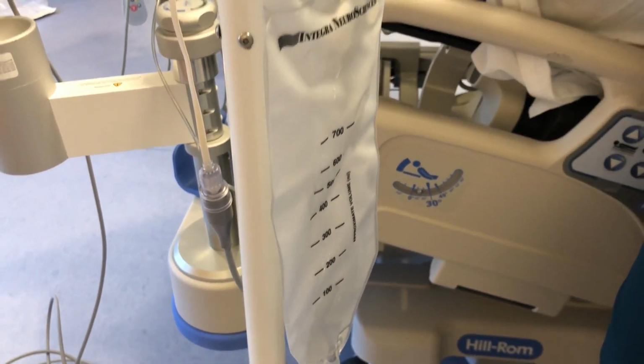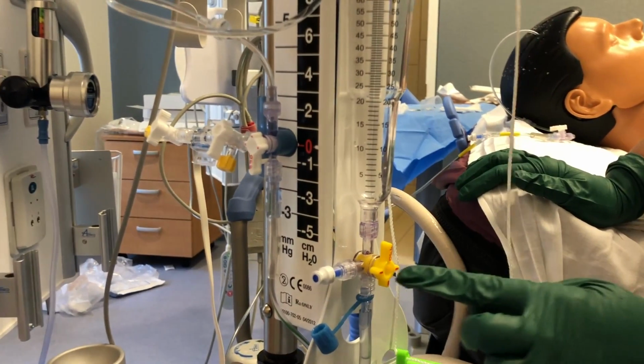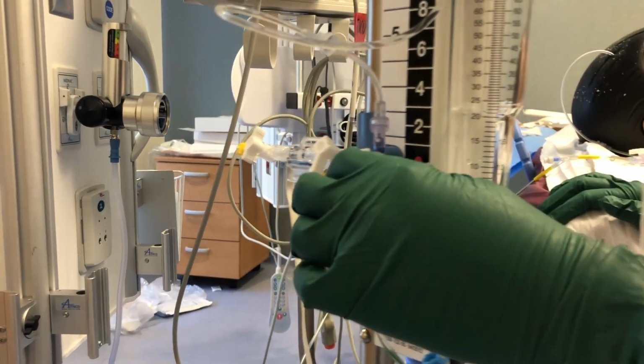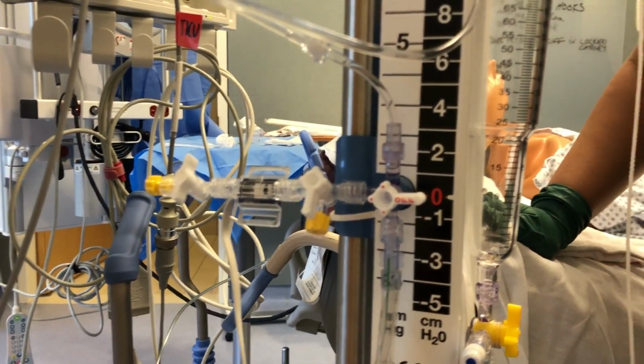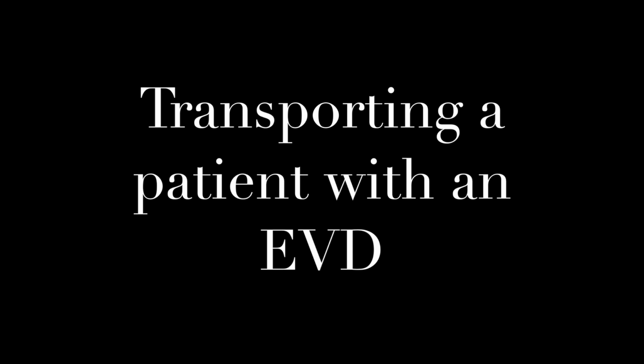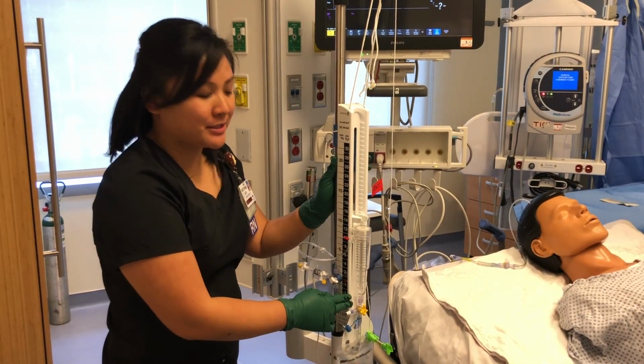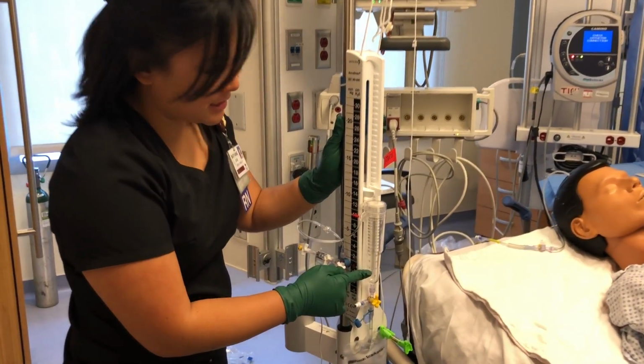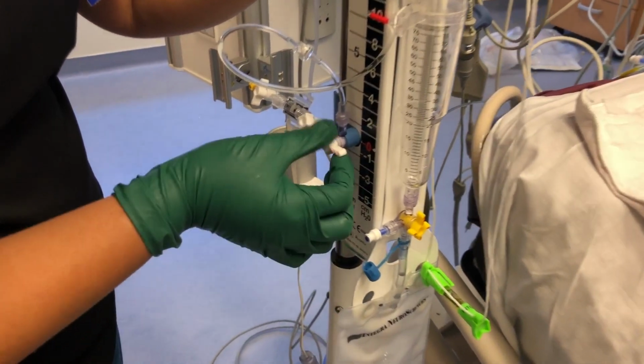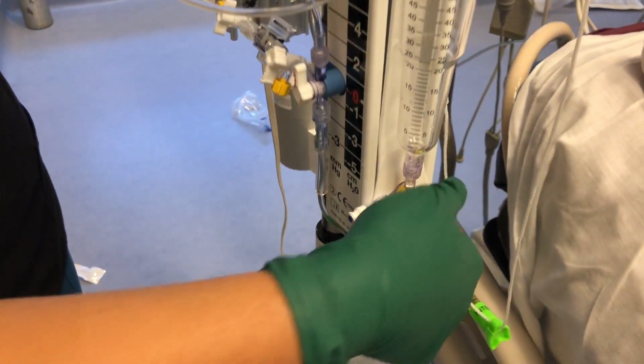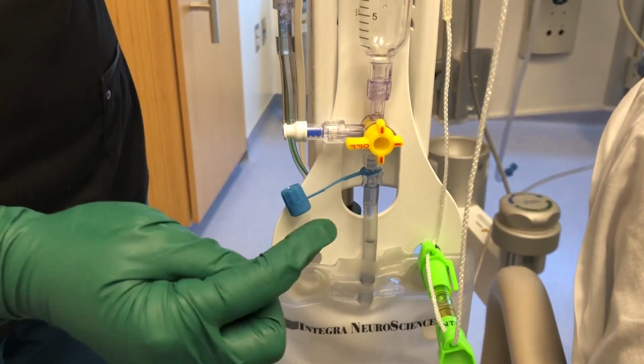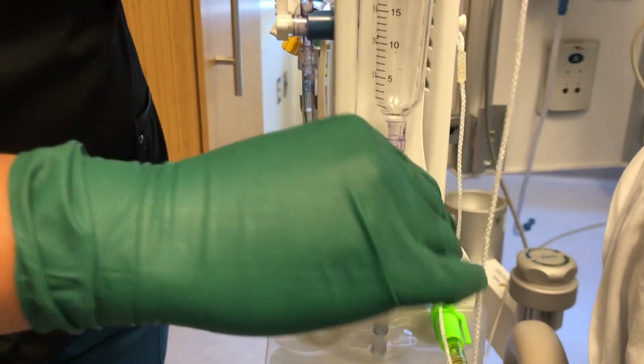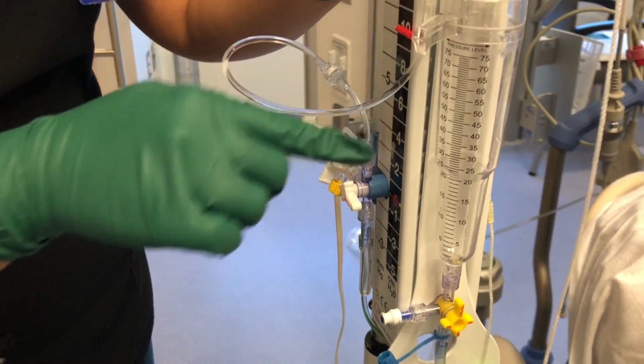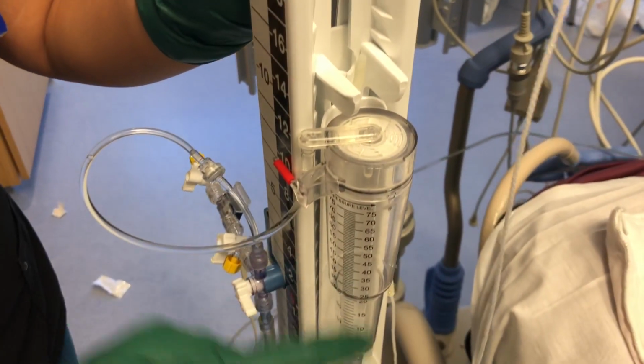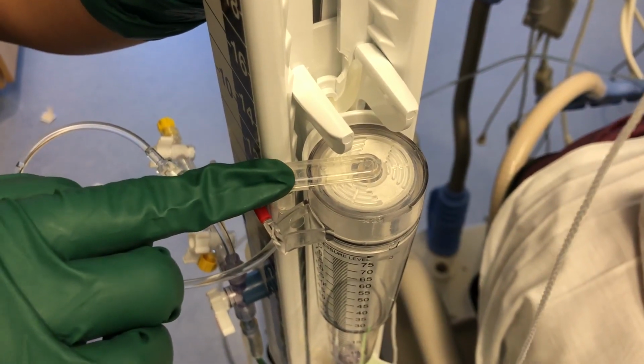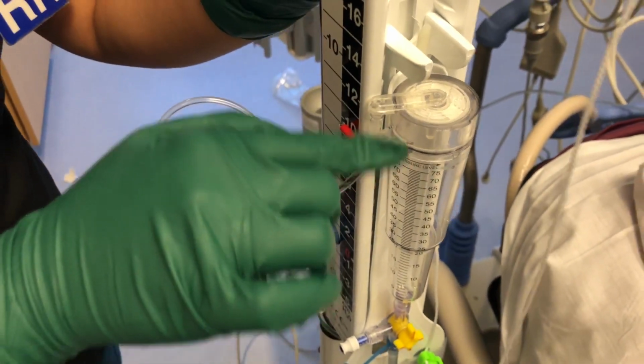And once that's done, always remember to turn off up to the chamber, and remember to open the drainage system so that CSF can flow back in. Before transferring the patient to any procedures, you want to make sure that the volume trough is completely empty. So remember to turn off to the patient, move the stopcock down to the side so that it drains to the bag, put it back up, open to the patient. The reason why we do this is because if the filter on top gets wet, it will cause the system to be clogged, and it will also be another risk of infection.